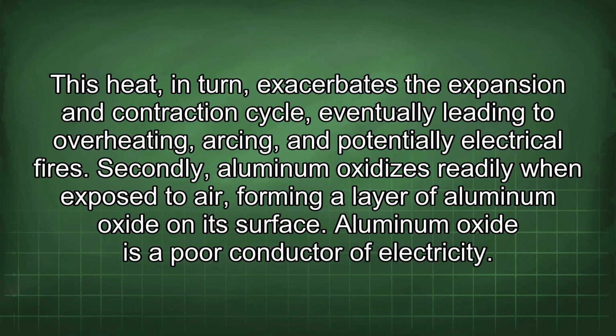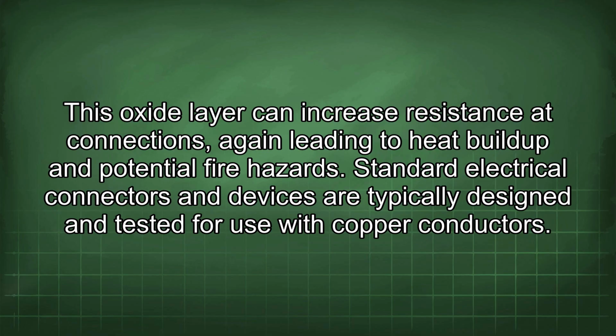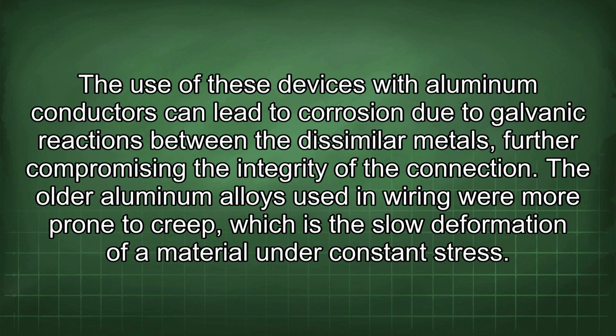Secondly, aluminum oxidizes readily when exposed to air, forming a layer of aluminum oxide on its surface. Aluminum oxide is a poor conductor of electricity. This oxide layer can increase resistance at connections, again leading to heat buildup and potential fire hazards. Standard electrical connectors and devices are typically designed and tested for use with copper conductors. The use of these devices with aluminum conductors can lead to corrosion due to galvanic reactions between the dissimilar metals, further compromising the integrity of the connection.